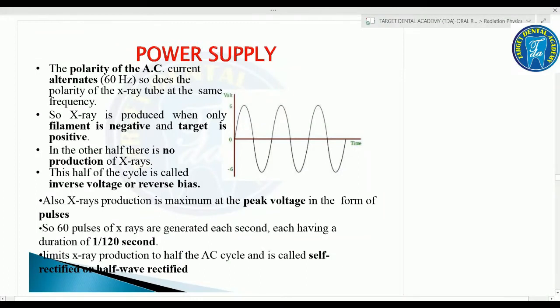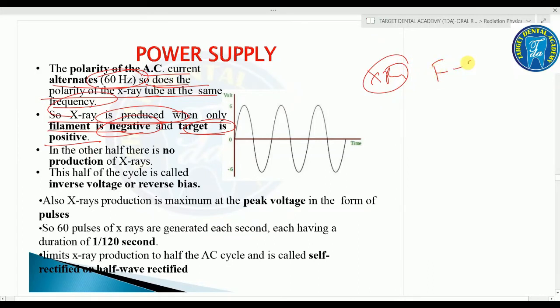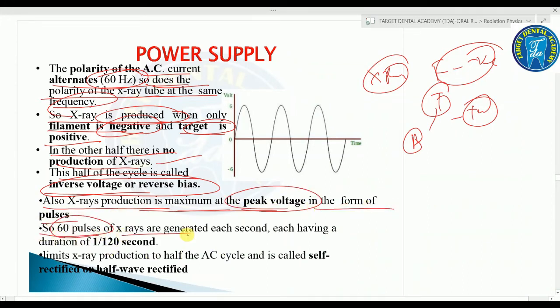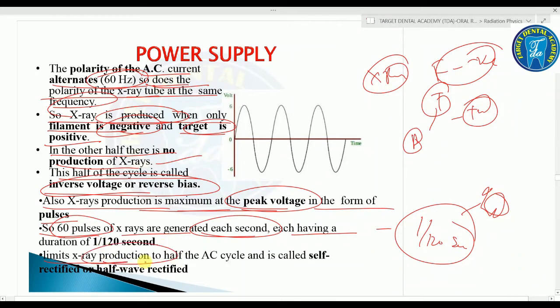The polarity of the AC current alternates at 60 Hz, as does the polarity of the X-ray tube. X-rays are produced only when the filament is negative and the target is positive; in the other half-cycle there is no X-ray production. This other half is called inverse voltage or reverse bias. X-ray production is maximum at peak voltage, generating 60 pulses per second each of duration 1/120 second. This limits production to half the AC cycle and is called self-rectified or half-wave rectified.